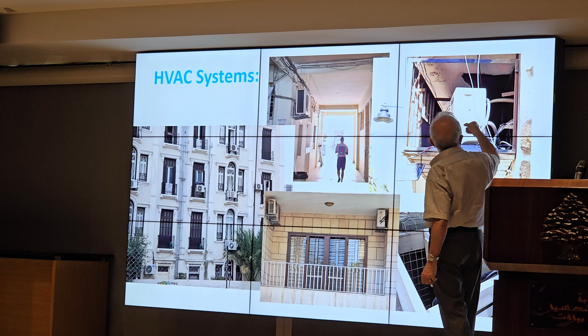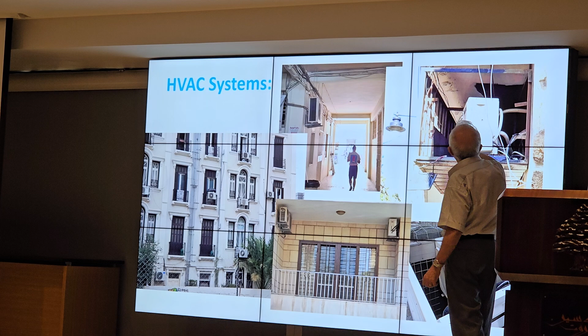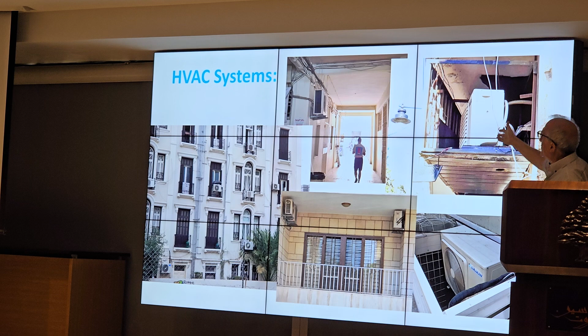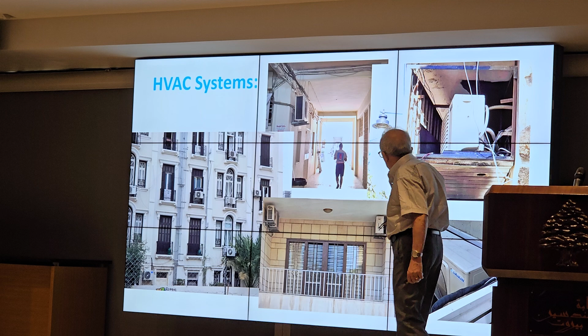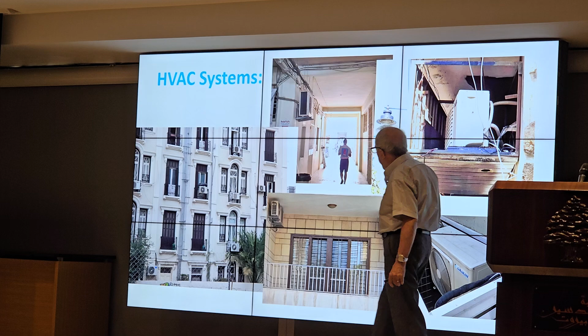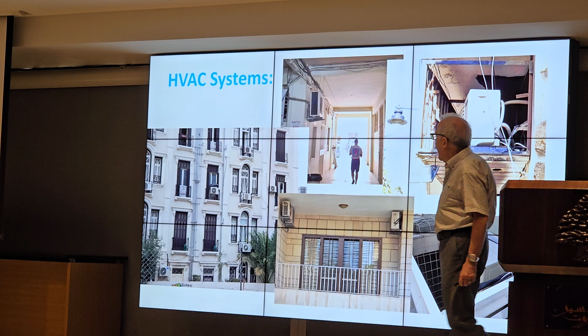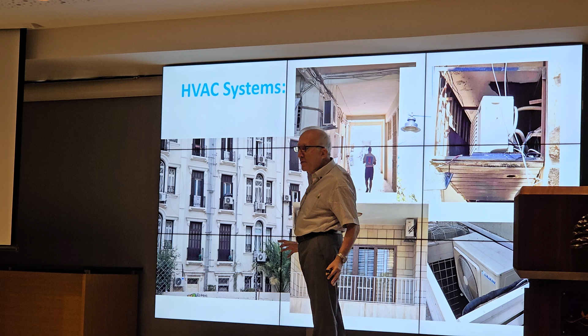Here for aesthetics, they have put louvers, and here too. So the air will blow, and on the other side you have the suction, so the same air will blow, and if you measure the temperature here, you can sometimes get like 50, and your condensation will be 60 or 65. Here also we have the condensers, one facing each other. So the hot air will be sucked by the second air conditioner.